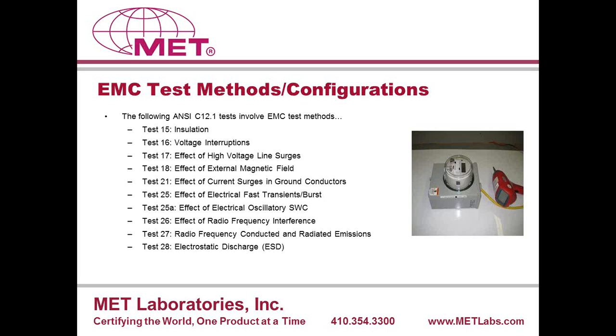The other test is effect of current surge in ground conductors. Now, this test is also something that is only required by ANSI. Most other commonly referenced standards do not call out for this spec. So what this test is, the name itself says it's a current surge. Although it says it's a current surge, it's not your typical lightning surge, where the lightning surge has a test parameter of 1.2 microsecond rise time over 50 microseconds, whereas this current surge is specified as having a rise time of 20 microseconds and a half time of 50 microseconds.